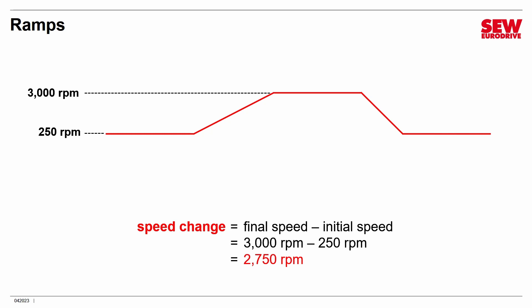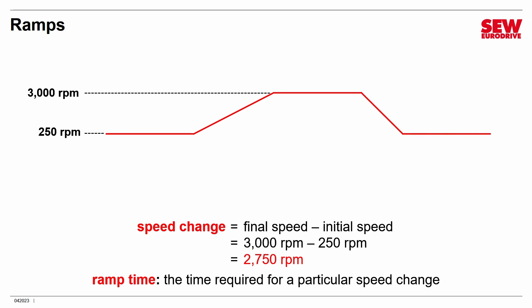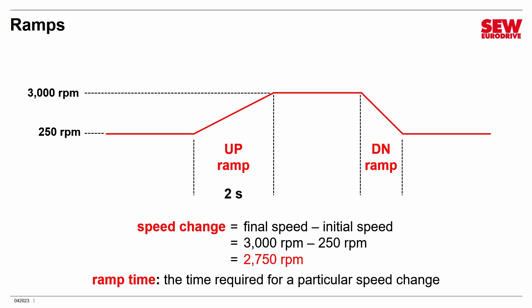Ramps also take time — those speeds don't happen instantly. We're dealing with things that may weigh vast amounts; you can't accelerate or decelerate them on a dime, it could take seconds or even longer with something really massive. In our example, we have an up ramp and a down ramp. The up ramp took maybe two seconds, the down ramp only one. So all the information we need to define a ramp is the speed change and how much time it took.